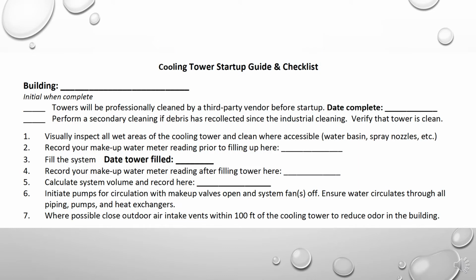So this is our startup guide and checklist. It looks just like the one we did last year. You want to put your building name, you initial that the towers were cleaned, and you actually record the date that that happened, and then you want to perform a secondary cleaning if you find that the tower has gotten dirty again since the vendor left the tower, and you can just get it cleaned up again, sweep it out, vacuum, whatever you need to make sure that you are comfortable with its cleanliness before you fill the tower.